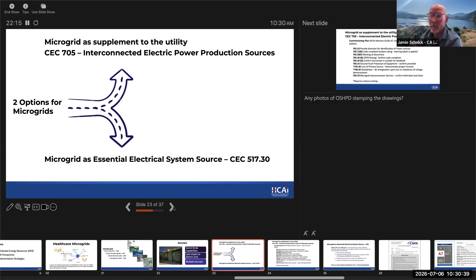Implementing microgrids to help harden the electrical facility involves two major options. One is to supplement the utility as a backup source, with code requirements found in Article 705, Interconnected Electrical Power Production Sources. The other option is to utilize the microgrid as an essential electrical system, which is permitted by code and found in the California Electric Code, Article 517.30.